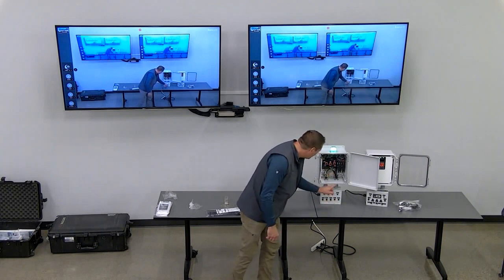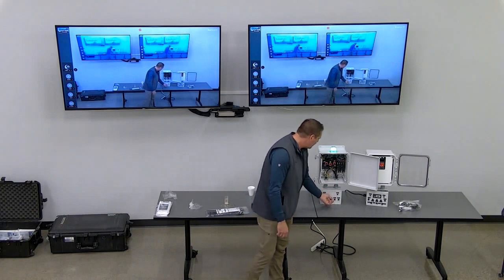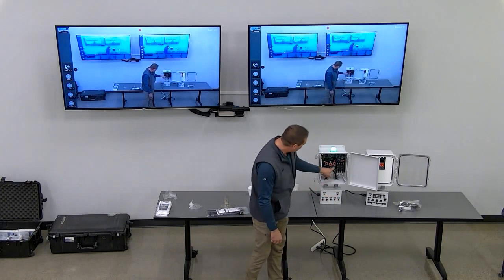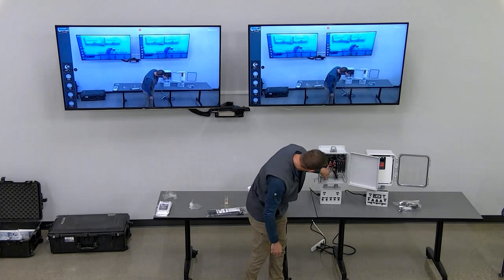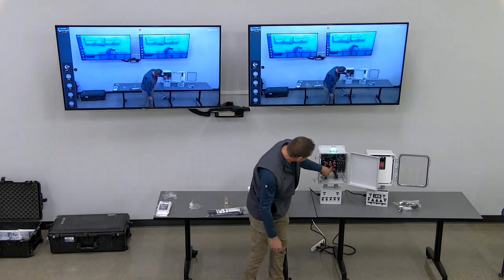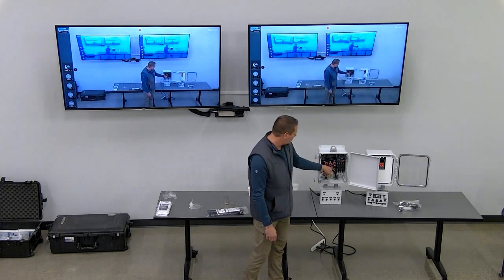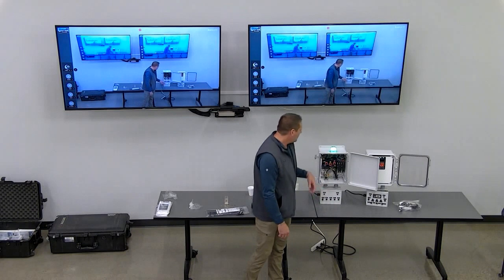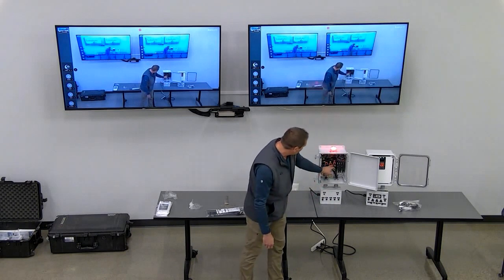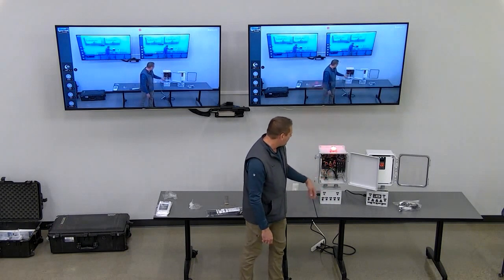So we have your low level or your off float coming up. Your lead float comes up, turns the pump on. You have pump run indicators here. Pump 1 is on. It gives you the status of each float, whether it's closed or open. Your lag float comes on, pump 2 and 1 are both on because they're both in automatic.